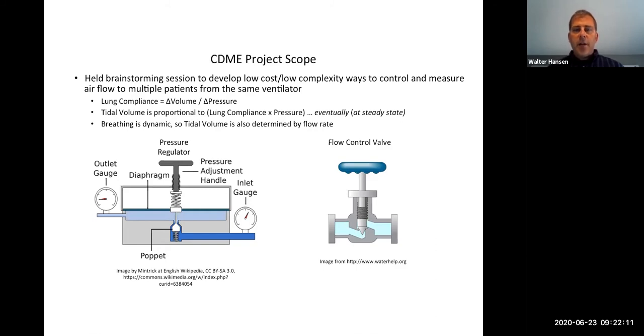As Dr. Hussain described, this is complicated not just by variations in patient lung size, but also by variation in lung compliance. The mathematical description of compliance is the change in volume divided by the change in pressure. So the volume of air received by each patient on a shared ventilator is proportional to their lung compliance multiplied by the supply pressure, eventually, at steady state. When I say at steady state, I mean the point when the pressure inside the patient's lung is no longer changing—that would be when the pressure inside the lung is equal to the supply pressure.